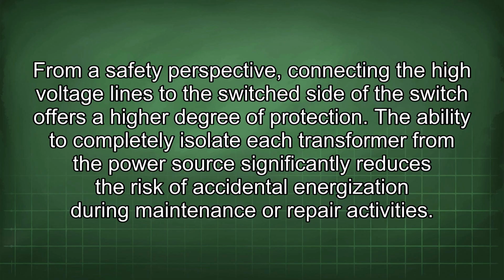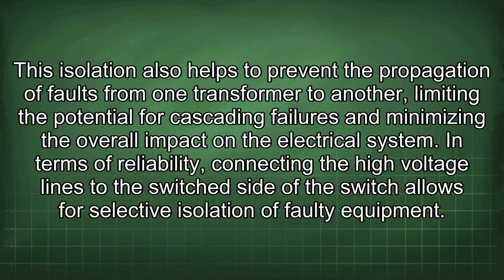From a safety perspective, connecting the high-voltage lines to the switch side of the switch offers a higher degree of protection. The ability to completely isolate each transformer from the power source significantly reduces the risk of accidental energization during maintenance or repair activities. This isolation also helps to prevent the propagation of faults from one transformer to another, limiting the potential for cascading failures and minimizing the overall impact on the electrical system.